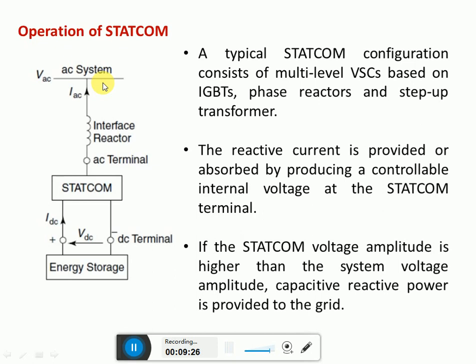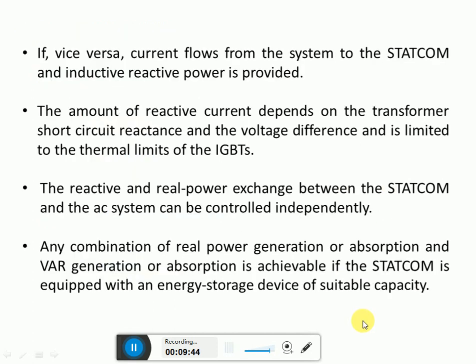compensator. Similarly, in the opposite way, when this E is less than the VSC, the system voltage, that time the current will flow in the opposite direction, so it can work as inductive compensator, or we can say it will absorb the reactive power from the AC system.